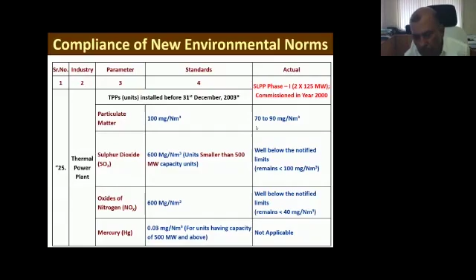Regarding SOx, there is a requirement of 600 mg/Nm³, but our emission is less than 100 mg/Nm³ because of addition of limestone as an additive, which reacts with the sulfur. Sulfur content in the lignite is almost 0.5 to 1%, though it is designed for up to 2%. It reacts with the sulfur, CaO reacts with sulfur to form CaSO4, which is gypsum, like sand. It comes out from our combustor itself and is used as filling material and for manufacturing bricks with fly ash, just like a substitute for sand.